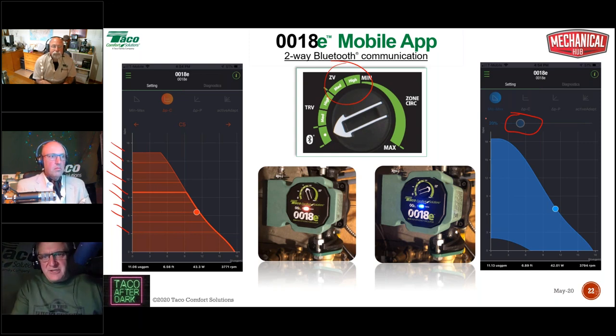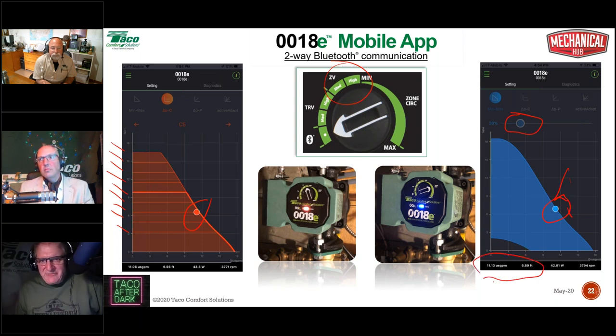Now, in every one of these screens, you see this dot. That dot represents the actual operating point of the system at that moment. All right, that's kind of cool. You can see where your system's working. So say I've got this thing set at 20% speed and I'm way the heck out here. All right, I'm on the far edge of that pump curve. And right now I look down here and it's telling me that pump's pumping at 11.13 GPM at just under 7 feet of head. And at this point, it's like at 42 watts.